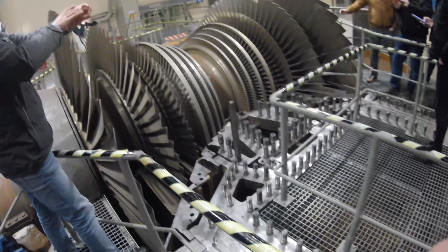It's two-sided: steam is coming from the middle, going to the center, and then going out to the outside. The reason we have two-sided turbines is, first, the weight is more balanced, and second, if you push the steam only in one direction, there is a force pushing that way. If the steam goes in both directions, the forces equal themselves out, so it's much easier to handle.